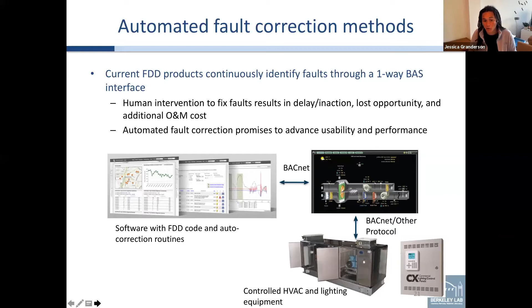The fault diagnostics tools I talked about ingest data from control systems one way: they pull data, analyze it, and present findings to a user. In this effort, we're looking to close the loop and open a two-way interface with the control system, implementing corrective action on a class of faults that can be corrected through controls and software—things related to control and scheduling. We can't fix leaky valves or stuck dampers without an actual wrench turn in the field, but this is what we're looking to do in this project.